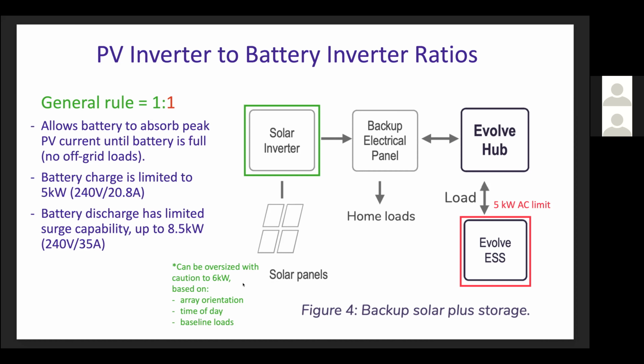And if you've got no way to derate that solar that's tied into the system that will be served when it goes into backup mode during a grid outage, if that can't be derated, as I mentioned with the SolarEdge inverter with the PRI interface on that inverter, then you must physically partition that PV array in order to not overdrive the PV that's attached to the backup loads panel. Again, the battery discharge has limited surge capability up to a maximum of 8.5 kW, or about 35 amps. And again, that's for about 5 seconds, that's the maximum.